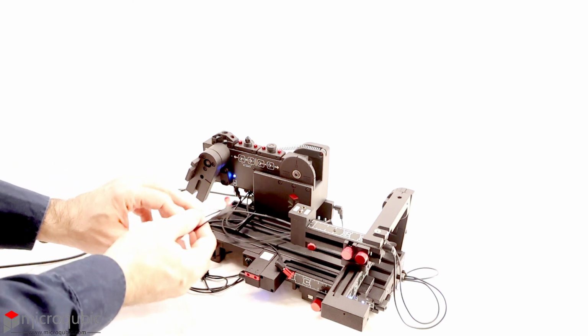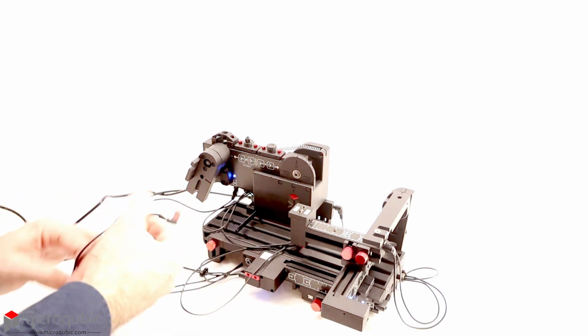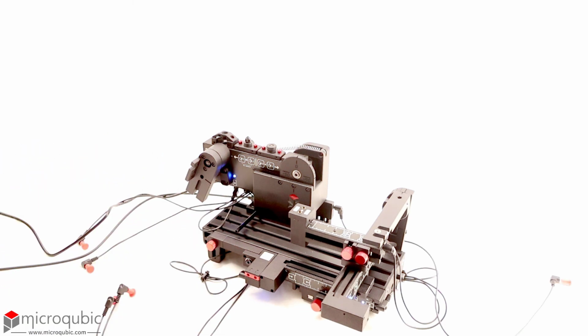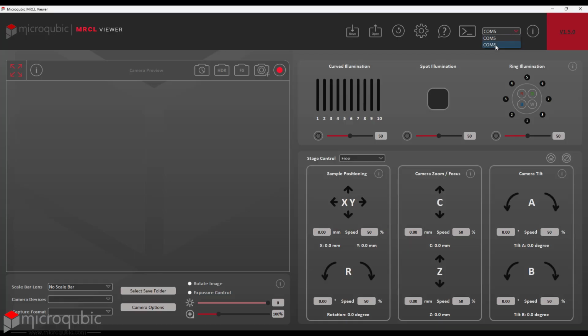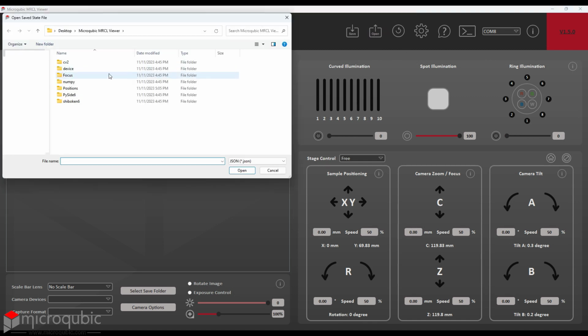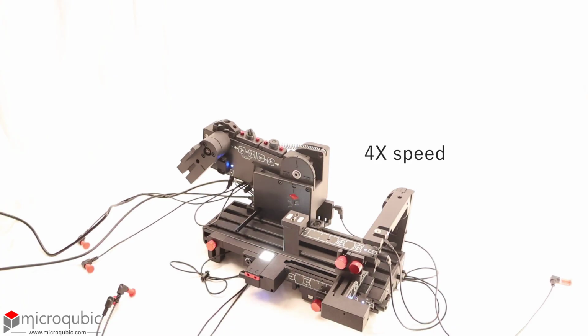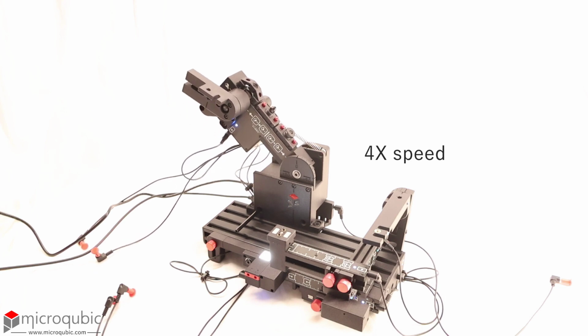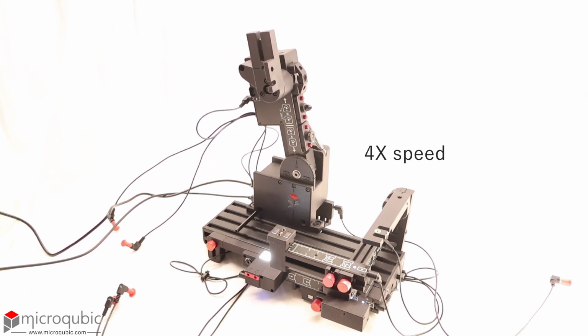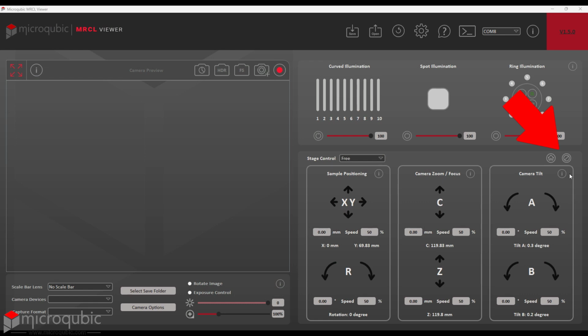Before proceeding to the next step, ensure the cables are untangled so they do not obscure the motorized movements. Now, select the COM port from the top right corner. This will establish communication with the microscope. Then, open the file named startup.json from the folder called Positions. This should move the tilting module slowly to its upright position. If you observe an issue, stop the motors using the emergency stop button and repeat the process.